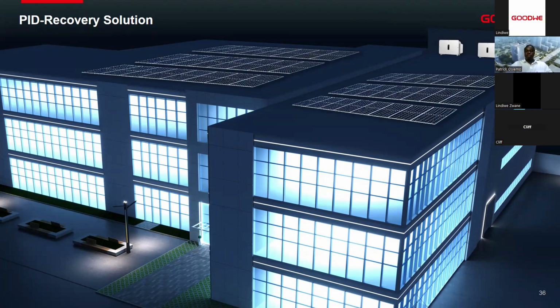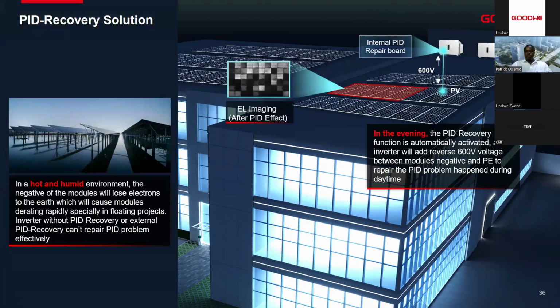Now with the GT series, PID recovery is an option. Once this is integrated with the inverter, during the night the inverter will be able to charge the negative part of the PV strings with around 600 volts to restore the electrons that had escaped from the PV panels. As a result, come the next day, the PV panel will at least be restored to its initial generating capacity. So that's how the PID recovery solution is very impactful to C&I solutions. Once you install the GT series in hot, humid, or mostly humid areas, you'll be restoring your PV panel generation capacity.